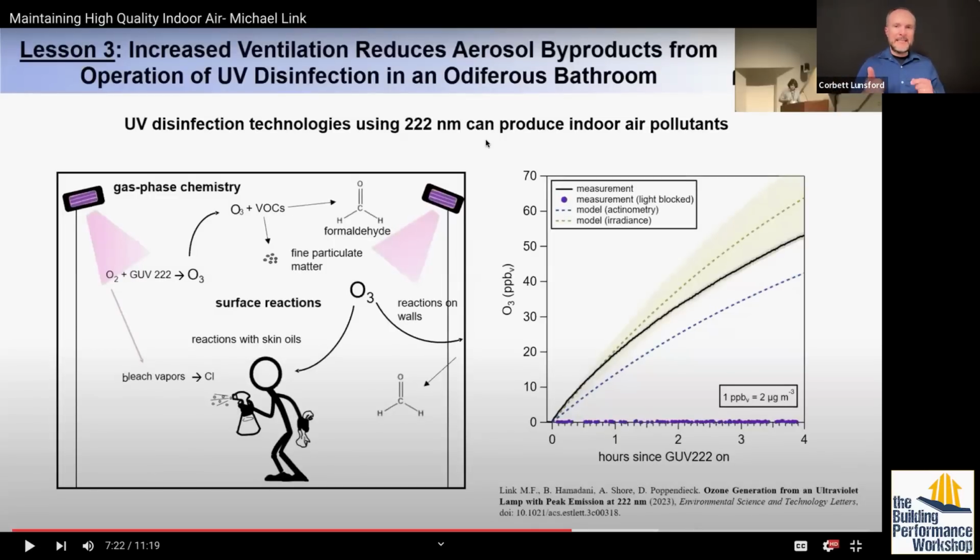Now, there is a standard on this that we're going to get to. The reason that people used these during COVID was because restaurants, like public places, were a little bit more worried than simple homeowners because they didn't want to get sued for killing a bunch of people. And so ASHRAE has this standard called 241. ASHRAE has another standard called 62.2, which I talk about a lot on this channel already. That's about residential ventilation. This is about control of infectious aerosols. And so it prescribes either ventilation, or if you can't do ventilation because your HVAC system isn't good enough, then you can do this disinfecting technology.